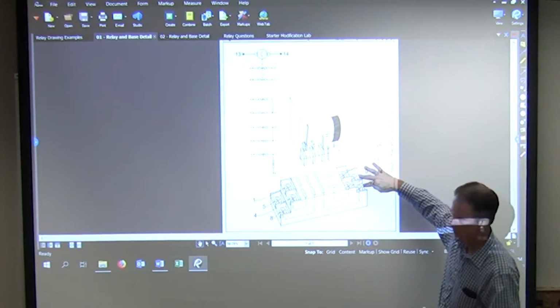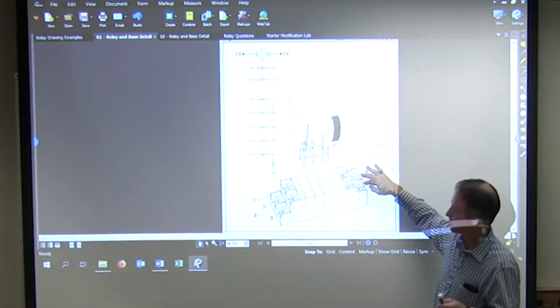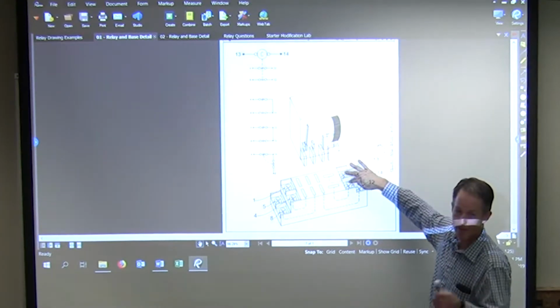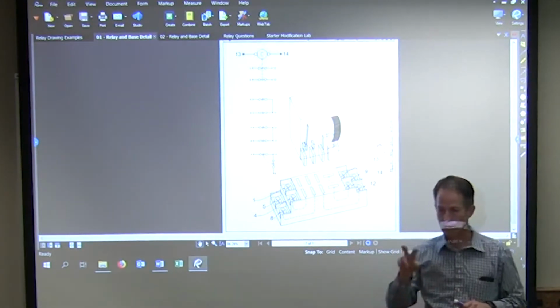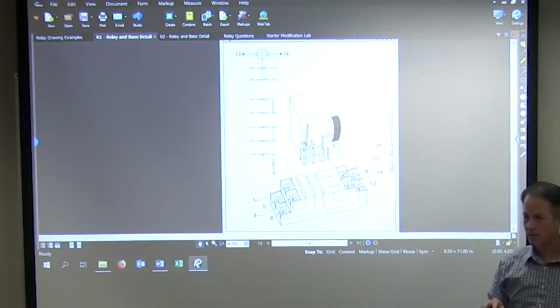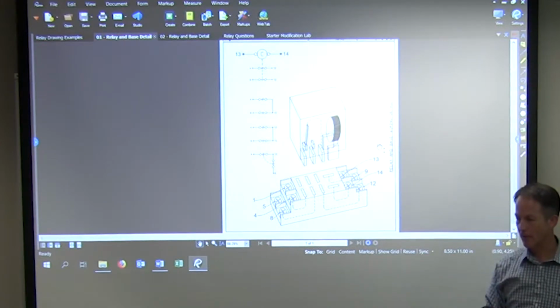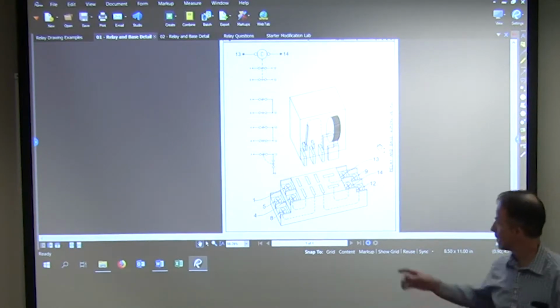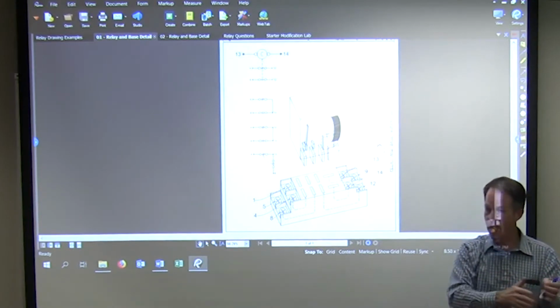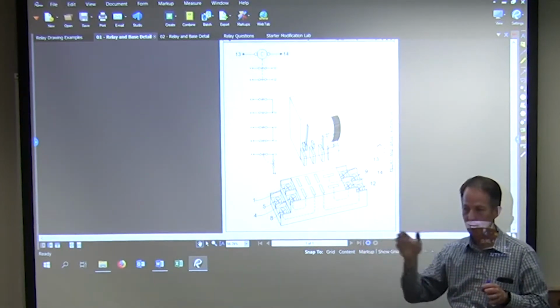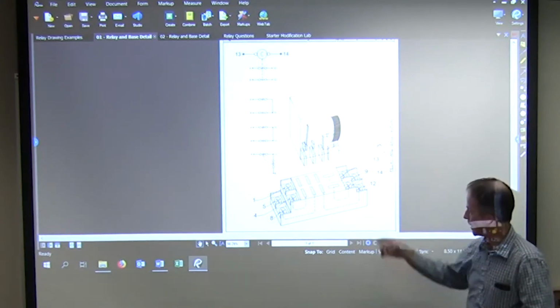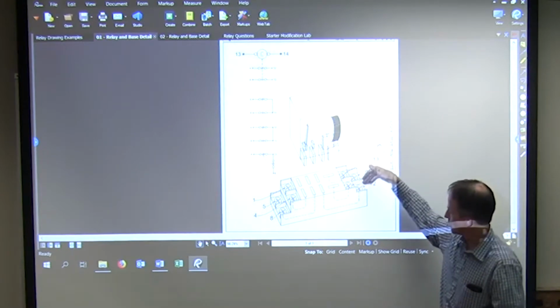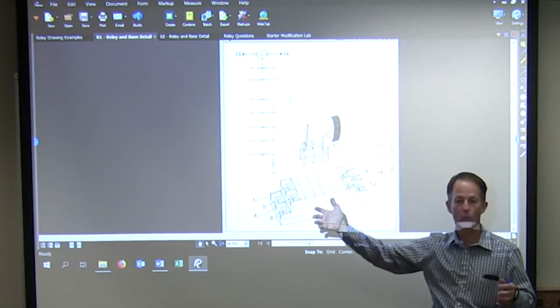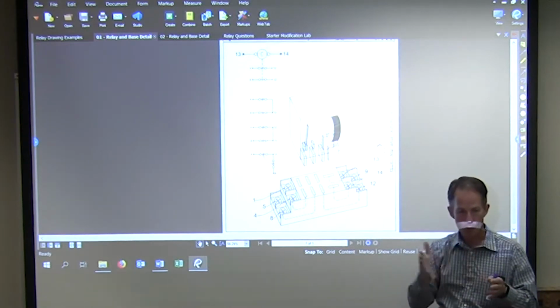What are these over here? So it's the common of the contact, right? Not the common of the circuit, just the common of the contact, and these are the coil. Now, are the coils polarity sensitive? If your relay is DC, yes, they are, but for AC, they're not. The one thing I would recommend if you're wiring a panel is to put all the 24 volt high, 24 volt low, and the common on the same sides consistently. Just be consistent. If you're going to number your contacts, start one here, then two, and do that through the whole panel so that as somebody comes behind you, troubleshooting makes sense.